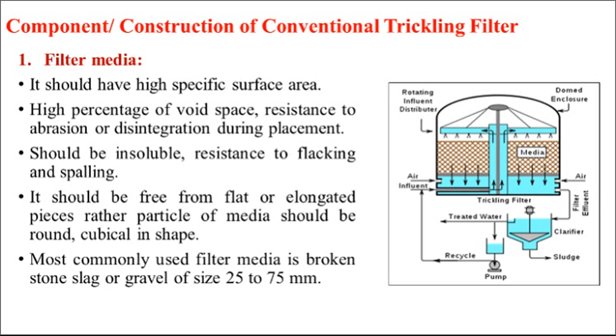The most important component of trickling filter is filter media. It should have high specific surface area, a high percentage of void space, and resistance to abrasion or disintegration during placement. The filter media should be insoluble and resistant to flaking and spalling.